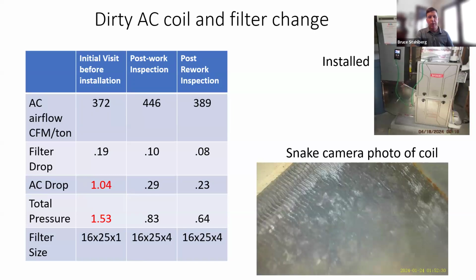This one, there's no audio, but on the very first visit, we had airflow. Actually, the airflow was spot on, 372 CFM. I'd be very happy with that. Our filter drop was not much at all, so that was really good. The AC drop over the coil was over 1 inch, which is more than twice what the manufacturer recommends. So that's a problem. This allows me to know that the air conditioning coil has a problem. I carry a snake camera and I was able to get a picture up in there, and you can see there's a lot of dirt on that air conditioning coil and it's plugged. So we could put a new furnace in, but we still can't get rid of the heat because we have a major blockage right above it. Post work, we did an inspection, and what I had called for is cleaning the coil and putting in a better 4-inch filter.